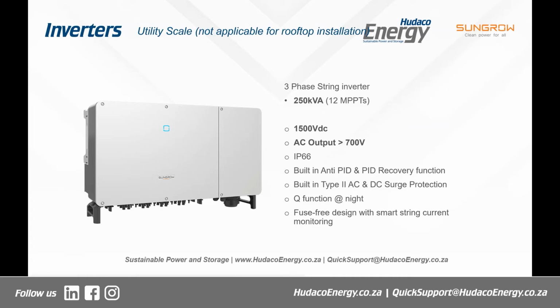But the biggest reason that it's not easily available is because your output is above 700. In fact, it's an 800 volt output, which means you have to be using transformers with this inverter range, okay? If you're doing a 5 megawatt project with your string inverters, this is the perfect product for you, okay? It is more cost effective. It is absolutely spectacular. It's reliable. Type 2 AC and DC surge protection built in. You've got your Q function at night, which is fantastic.